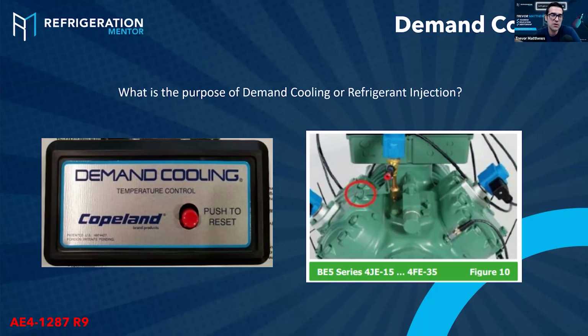I didn't really know what it was. So I was told, okay, because the discharge gets warmer with a high compression ratio, we need to inject some refrigerant to cool it down so it doesn't burn out the oil. But it didn't matter. I've seen so many R22 low temp compressors where you look in the sight glass, it could be a Carlyle, it could have been a Copeland, and it's brown and black in there just because it was running too hot. These compressors were just running too hot. Then 404 started to come into the industry, and 404 does not run as hot as R22. So all of a sudden on low temps, you didn't need demand cooling anymore. You could get away with just a head cooling fan.